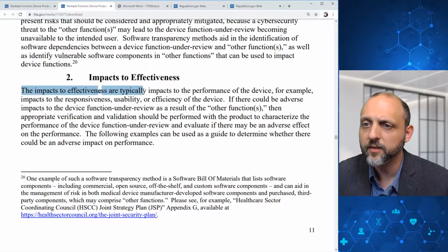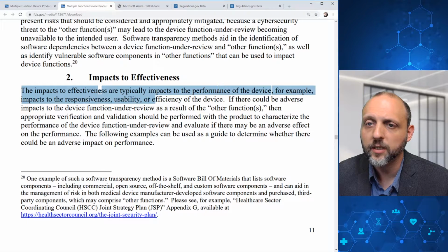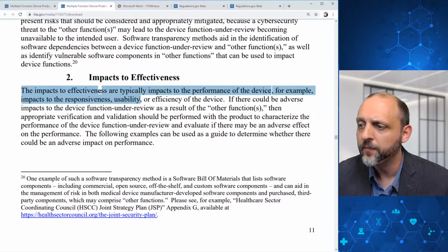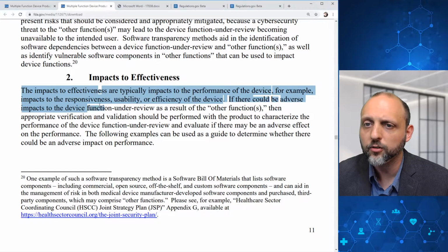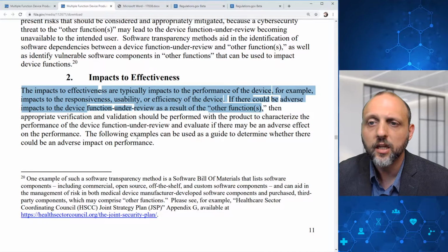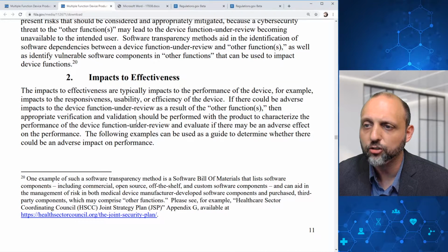The impacts to effectiveness are typically impacts to the performance of the device. For example, impacts to the responsiveness, usability, or efficiency of the device. If there could be adverse impacts to the device function under review as a result of the other functions, then appropriate verification and validation should be performed with the product to characterize the performance of the device function under review and evaluate if there may be an adverse effect on the performance.